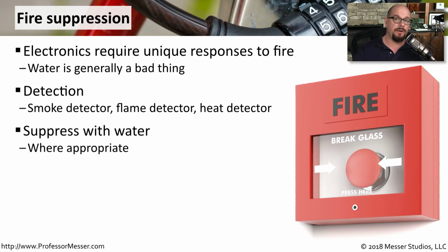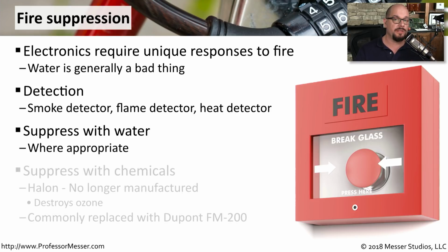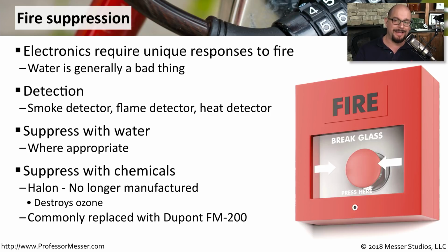If the fire is in an area that does not have electronics or a lot of power systems, you may be able to suppress it with water. But most of our modern data centers use chemicals to suppress this, thereby protecting the power and the electronics that are in the data center.